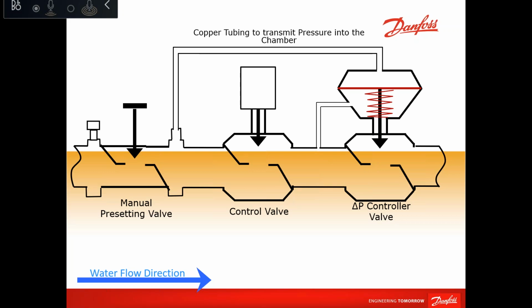So how it works, this is, by the way, the general concept of PICV. We will be touching on Danfoss PICV later. It's very simple, and any PICV should work this way. There is no different technology. It's the same: a differential pressure controller sensing the pressure before and after a control valve, and closing and opening. There are different technologies, but the same scenario. The tube will be before the setting mechanism and not after.